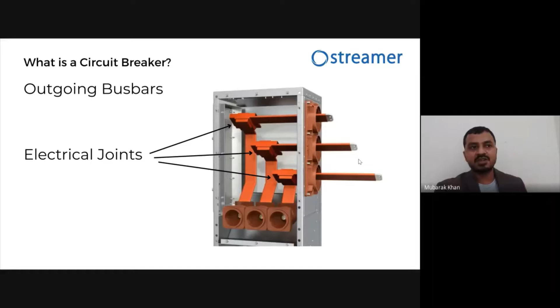Okay. Circuit breaker connections normally, now coming to the circuit breaker area, this is a circuit breaker. In the circuit breaker, the parts where the connections are made are these ones, which are known as tulip contacts or jaw connections or the spring loaded joints. Okay, tulip contacts, jaw connection or the spring loaded joint. If you see close up, it looks like this. These are the links which are spring loaded, and they come and get connected very tight on the other female part. This is the spring-loaded joint connection for the circuit breaker.